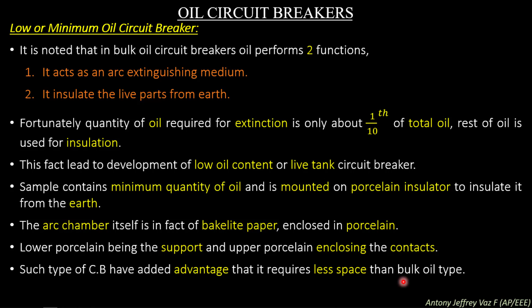So the minimum oil circuit breaker which we are going to design has two porcelain bushings, one at the lower end and the other at the upper end. The lower porcelain will act as a support, whereas the upper enclosing porcelain will house the contacts of the circuit breaker. Such types of circuit breakers have the added advantage that they require less space than bulk oil circuit breaker types.